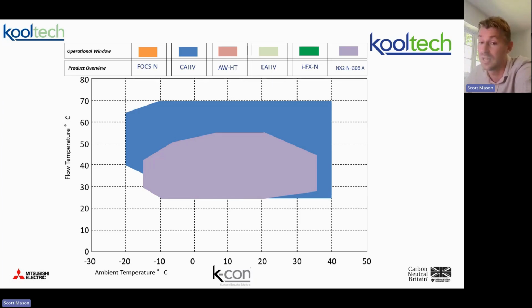If you don't want 60, absolutely fine, but then obviously you just need to do the relevant pasteurization regimes and whatnot. And actually distributing at 50 probably is a little bit low on a potable store system, because you want to be returning at 50 really. So generally when we see hot water at lower temperatures, it's more 55, and then we top up and pasteurize rather than being down at the 50s.